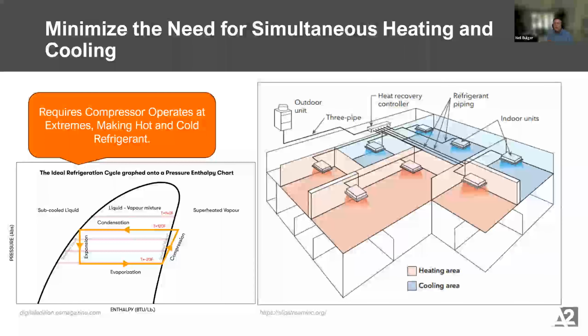Though when we look under the hood at the mechanics of how the refrigeration process works, if we have to heat and cool at the same time, we need that compressor to be working its hardest. We need it to make the hottest refrigerant it can for the zones in heating and then the coldest it needs for the zone in cooling. And that can actually make the compressor use more energy or operate at a less efficient point than if we just had a better envelope that might reduce the challenges of simultaneous heating and cooling. A lot of that occurs when we have a poorly insulated envelope where we have single pane windows. So it's there, but I would actually reverse the general design theory and say try to minimize it, but use it as a backup.